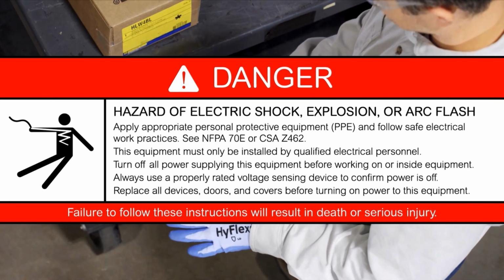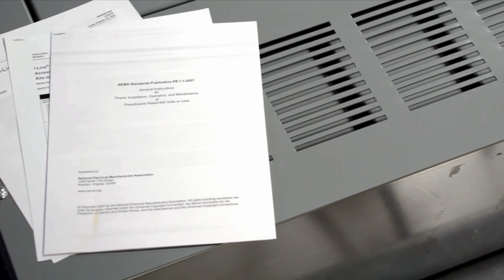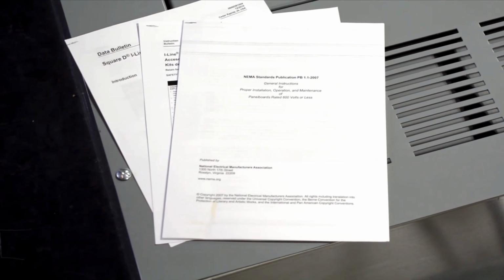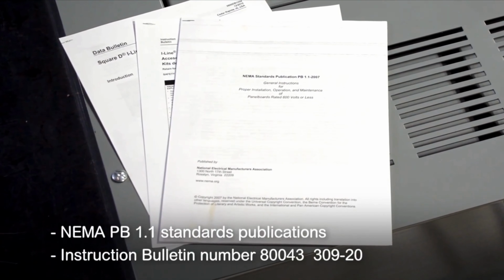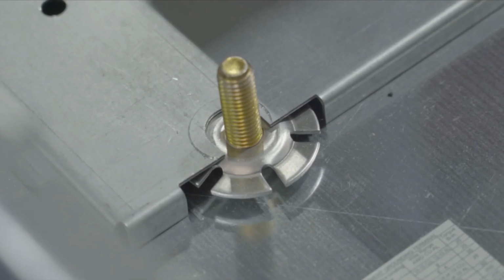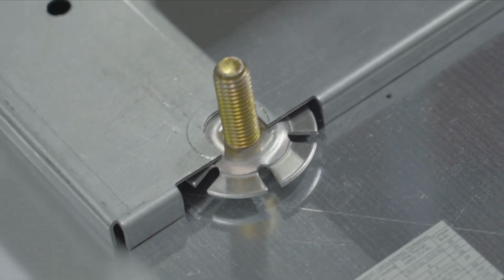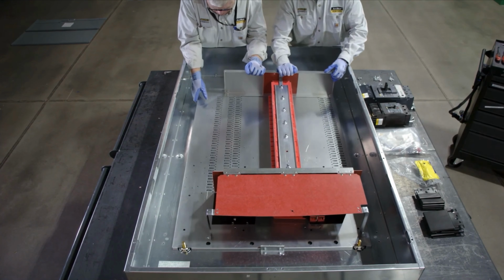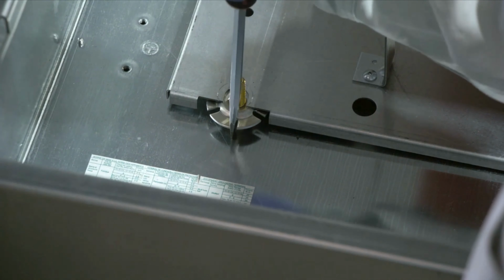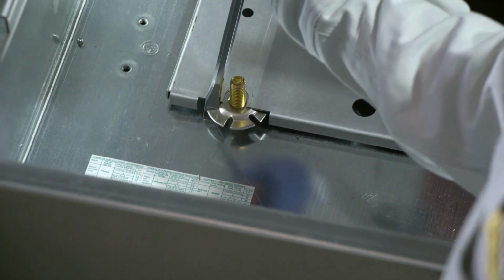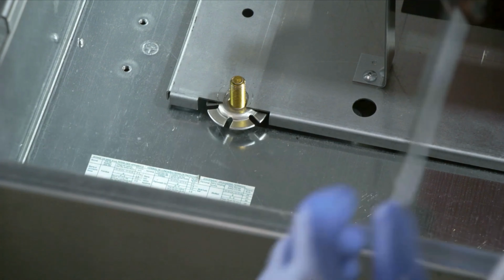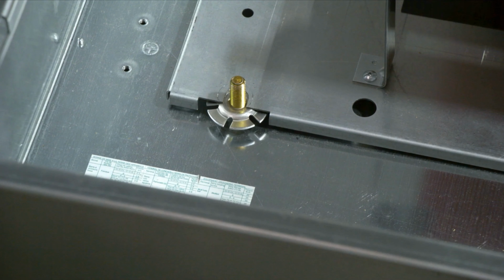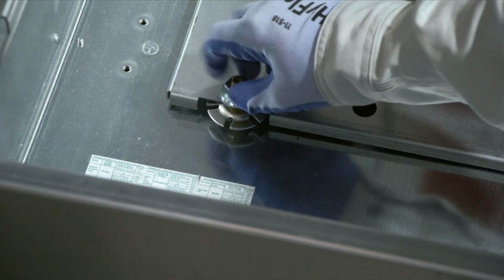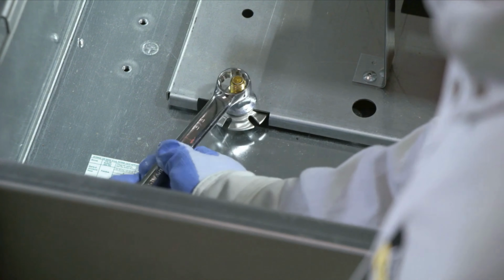For those of you mounting the I-line interior into the I-line enclosure on-site at a facility, refer to the instructions found in the NEMA PB 1.1 standards publications and instruction bulletin number 80043-30920. Start by installing one elevating nut on each enclosure stud. Set the interior on the enclosure studs and secure with the flange nuts as shown. A screwdriver blade may be inserted in the elevating nut slot to facilitate adjustment. Adjust each elevating nut to maintain a maximum distance of 0.125 of an inch between the interior trim and the front door assembly. Tighten the flange nuts against the pan.